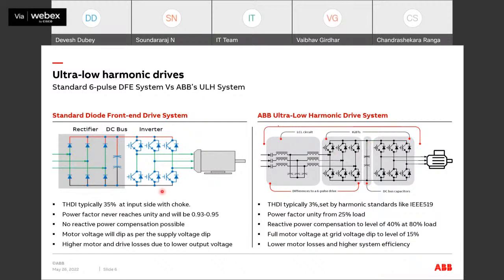What are the benefits? The inverter in both cases will be IGBT based. What is the benefit of having a low harmonic drive system or active front-end drive system? When you are using a diode front-end drive, the THDi, the total harmonic distortion, will be in the range of 35% at the input side with the choke. While when we are using an active front-end drive or a low harmonic drive, the THDi will come in the range of 3%, which is as per the standard set by IEEE 519 norms.